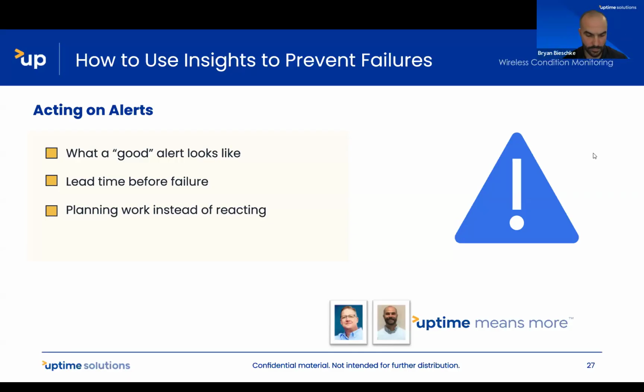Agree—the only thing to add is, for people listening who use VFDs, make sure they're set correctly. I've been part of so many organizations with brand new VFDs installed and running for years, only to find out they're not even configured right. You were losing power, wasting electricity, having unexpected faults for no reason other than the VFD not being programmed correctly for the job.